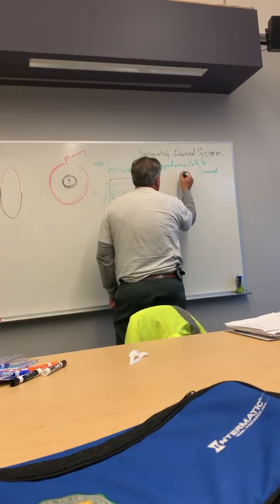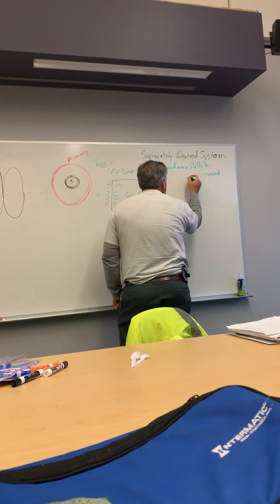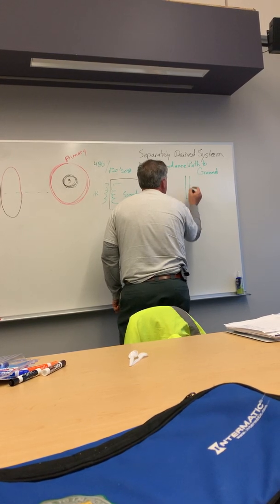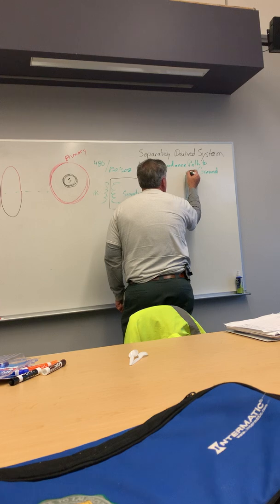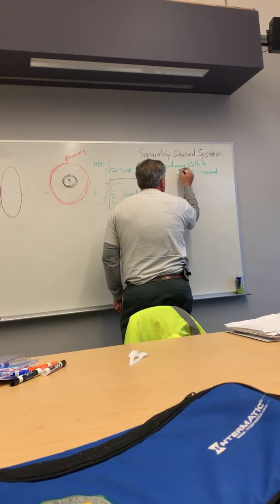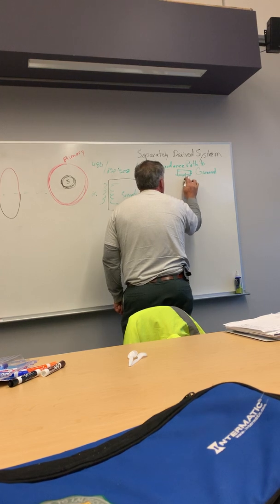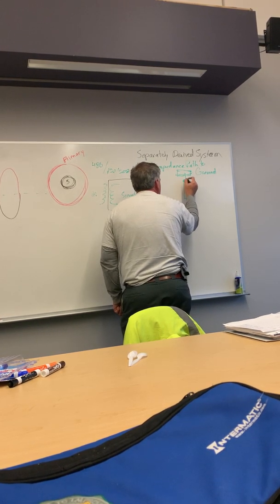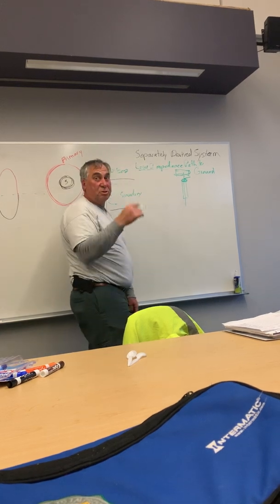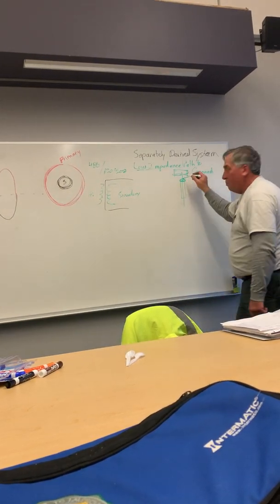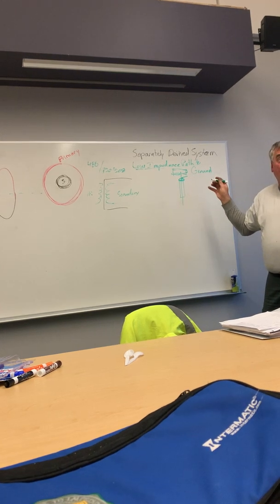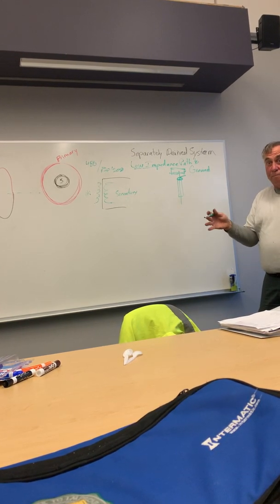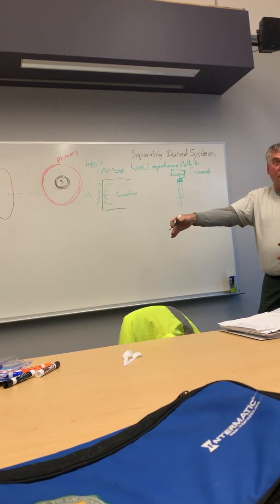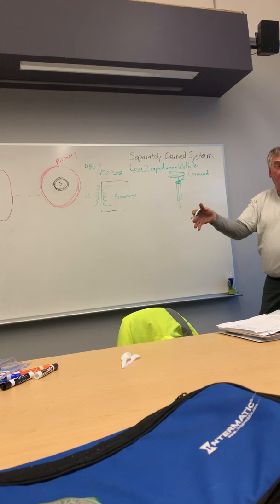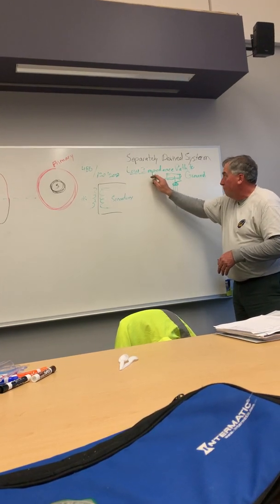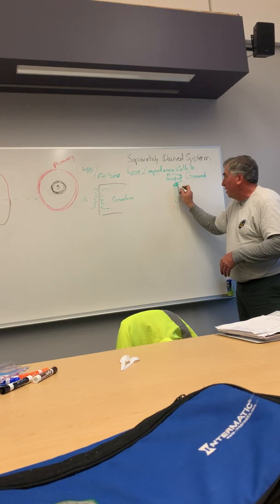There are a lot of times when people want to put grounds in rigid pipe, or say metal pipe. So you've got a ground wire coming through there, and they want to make sure that we bond this when it comes through the pipe. I'm going off on a little tangent, because anytime we have an extreme fault current, it could be thousands of amps immediately, like you just dumped the whole PG&E grid on this ground because you got a dead short. That's why they call it low impedance: you want to make sure that this is bonded and it all becomes the same.